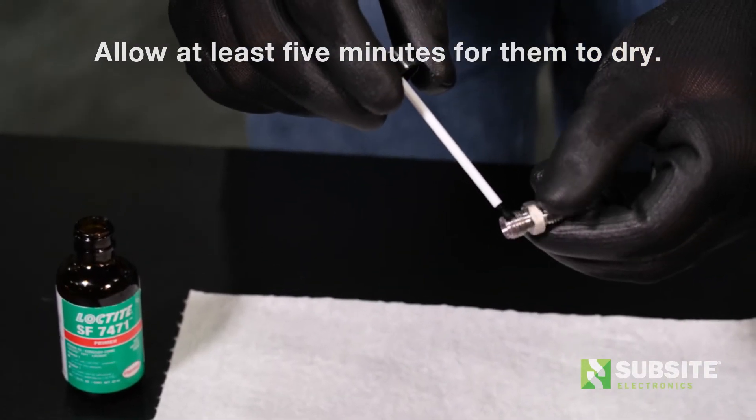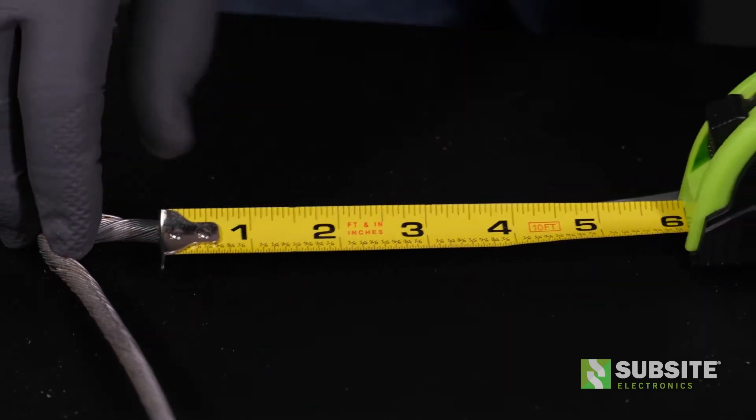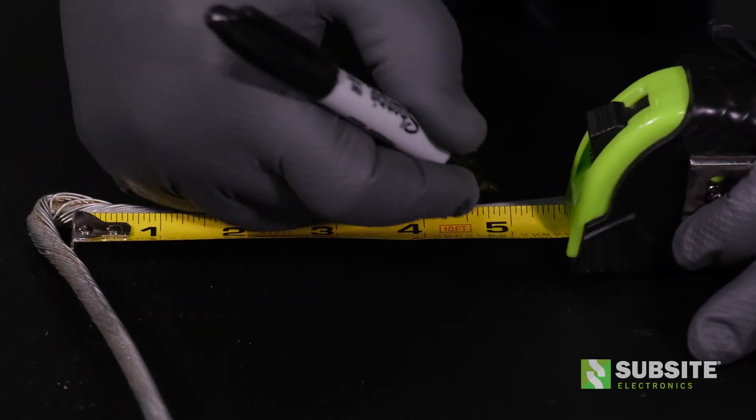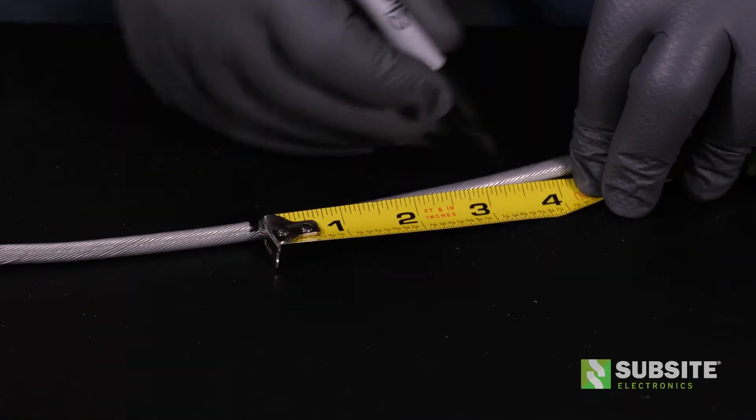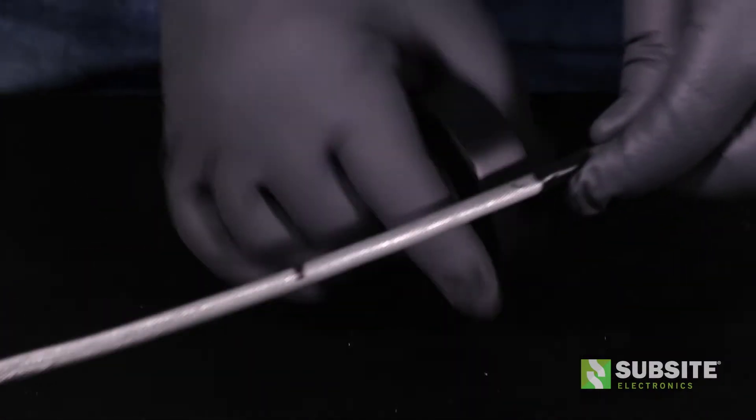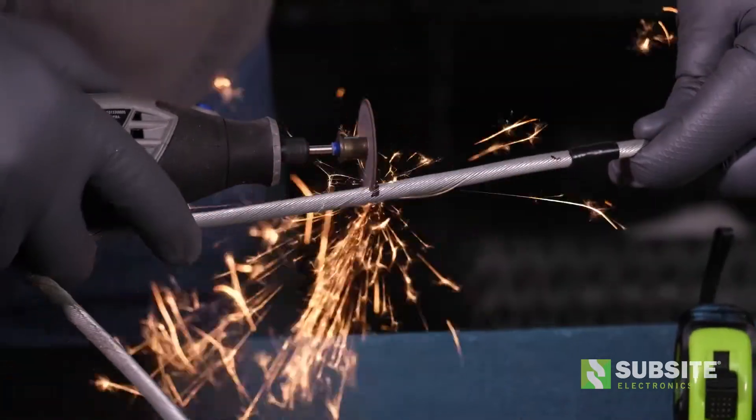Now you can begin the re-termination process. Locate the damage on the cable. Measure 5 inches from the damage toward the reel. This is where you will cut the cable. Measure another 3 inches from the cut location toward the reel and wrap black tape around the cable to prevent fraying. Using the Dremel, cut completely through the cable to remove the damaged section.